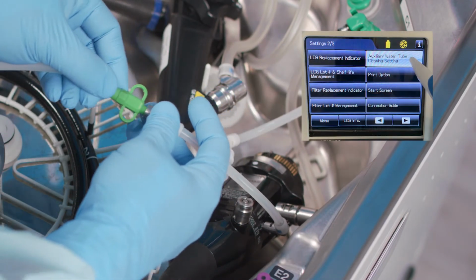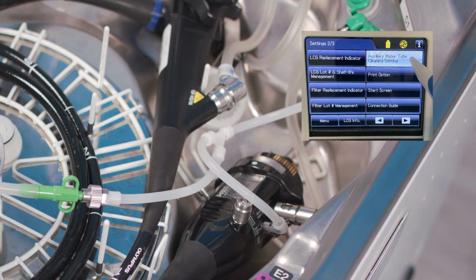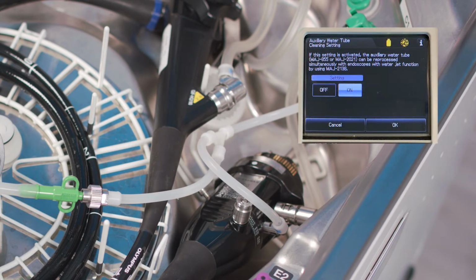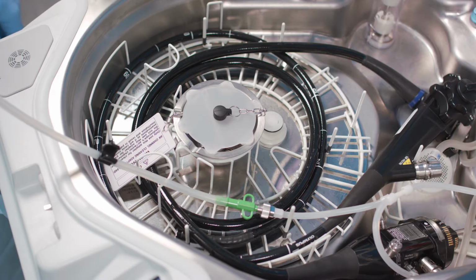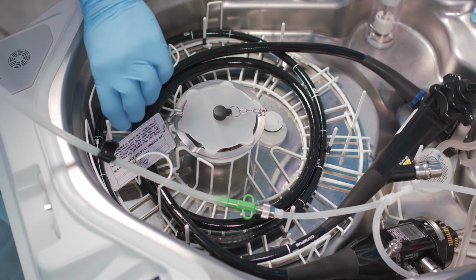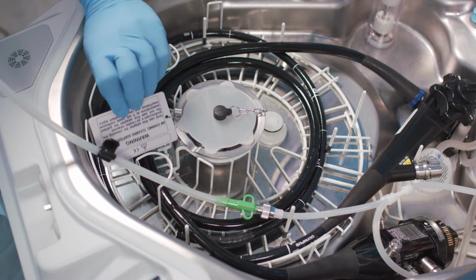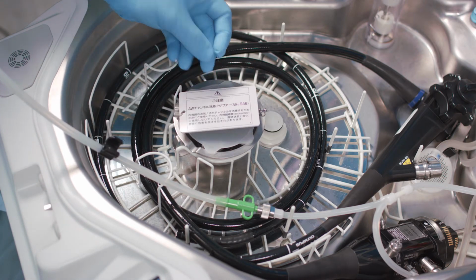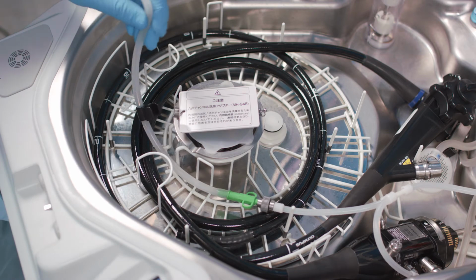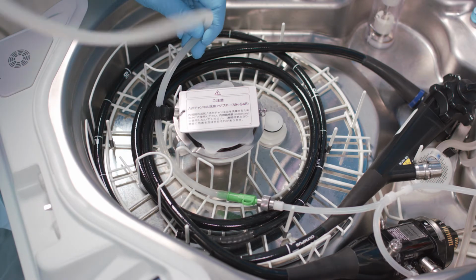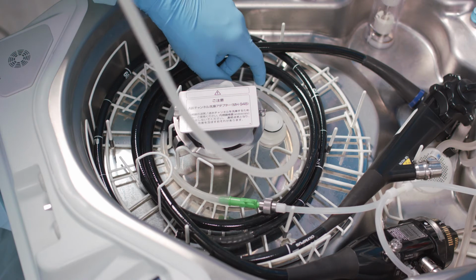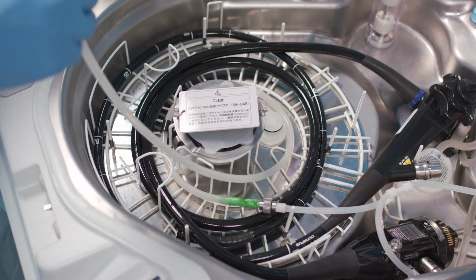If reprocessing the auxiliary water tube together with the endoscope, the auxiliary water tube cleaning setting should be activated. Before setting the auxiliary water tube, you may want to temporarily place the indicator plate of the air-water channel cleaning adapter on the washing case while loading the auxiliary water tube. This will keep it out of your way for the steps to come.